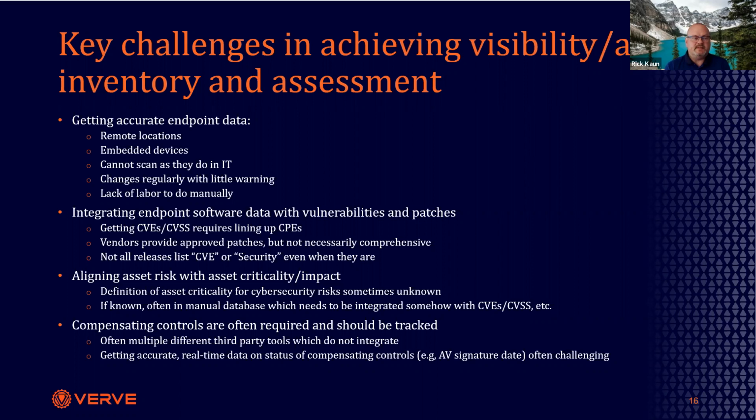We had Siemens come out and apply all their patches, everything that they'd approved. They sent out the technicians, everything was perfect. We then looked at the patching dashboard after they left, and there were still 800 missing patches. And we asked them, and they said, well, we don't test those because those are core to Windows, not core to Siemens software. And that's as far as they can go.